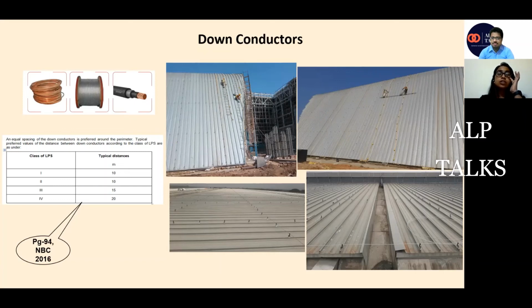There was a misconception earlier: put 4 air terminals at the 4 corners of the building, take 4 down conductors from the 4 corners and earth them, and the lightning protection system is done. But now, after IEC 62305 came in, lightning protection designing has been standardized. The risk calculations are very important now, and everything is standardized. Like if I am using the mesh method, the mesh size should be so and so, which is given in the standards. Also, for the laying of down conductors, the minimum distance between two down conductors is fixed by the standard.